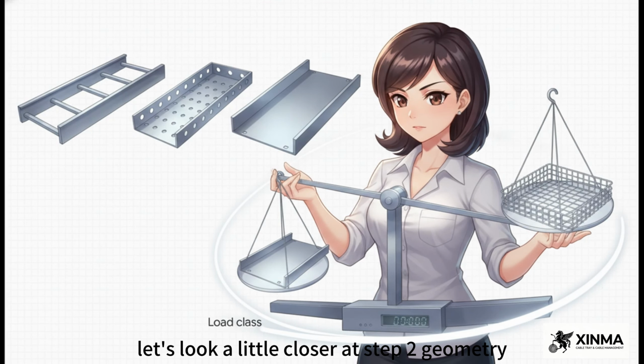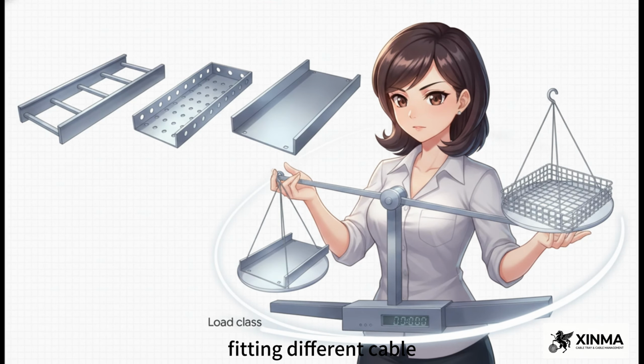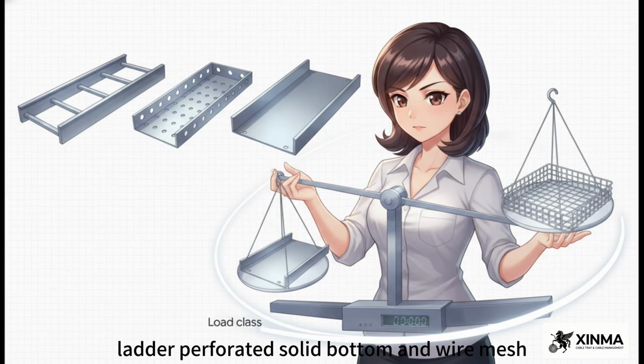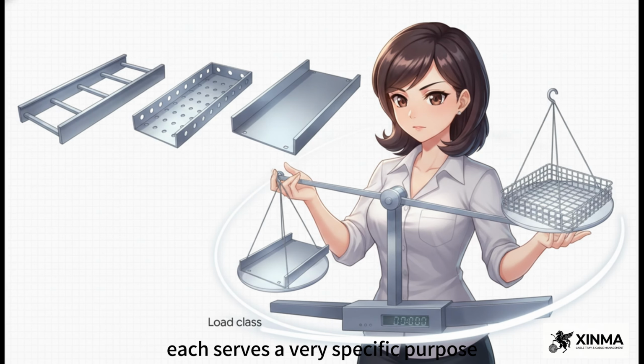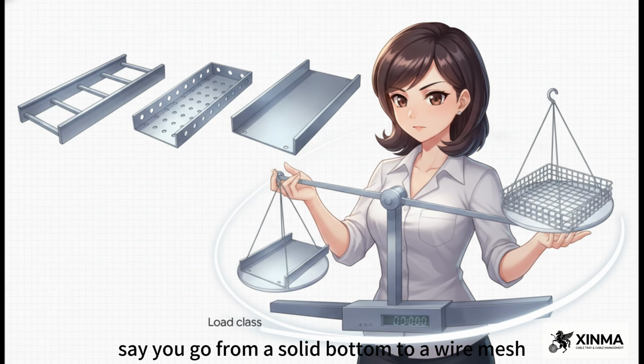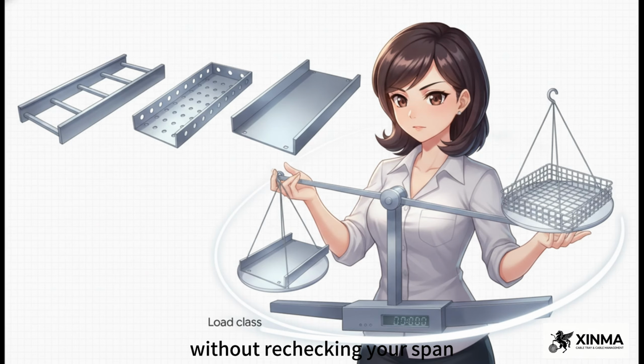Let's look a little closer at Step 2, geometry, because this is where a lot of people trip up. You generally have four main options fitting different cable functions: ladder, perforated, solid bottom, and wire mesh. Each serves a very specific purpose, but here is the critical warning: if you switch the tray type, say you go from a solid bottom to a wire mesh, without rechecking your span, you will completely alter the load class.